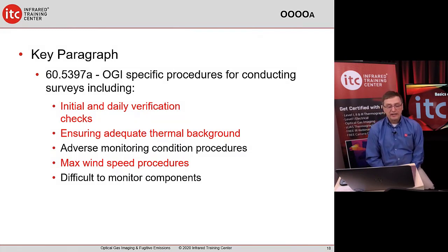Also, QuadOa said there should be a process for initial and daily verification checks. Fantastic. Just last week I had a class, and one of the students turned his camera on and looked at another student. That student was 145 degrees Fahrenheit. And whoever had the camera before was playing around with the parameters, emissivity. He says, hey, lesson learned. And I said, that's in all of our courses, so a verification check that the camera works is not a bad thing. And also, extremely important, is to ensure that we have adequate thermal background.